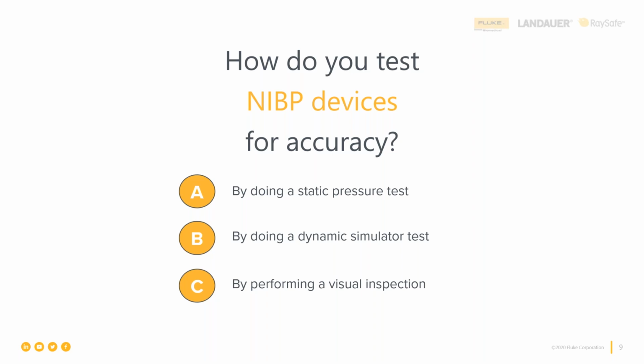You have to have a transfer standard or a primary standard to be used as a comparison. That is something that is absolutely accurate. It has been calibrated with traceability all the way to SI units of measure. So the only way to assess accuracy, and it doesn't matter whether the technology is inflationary oscillometry or deflationary oscillometry, or even if it's that aneroid gauge that is used for doing auscultatory pressure assessment, the only way to assess accuracy is by static pressure level tests, period.